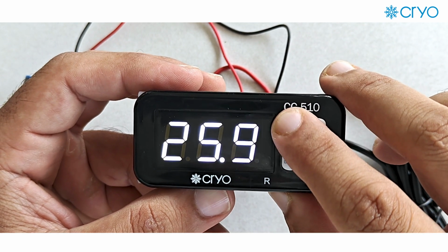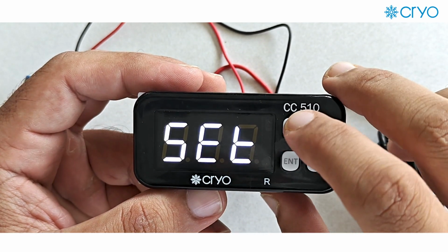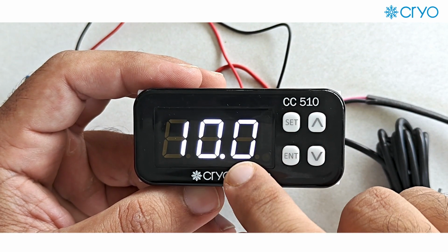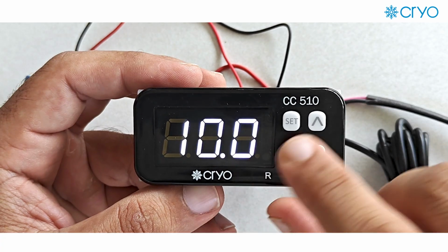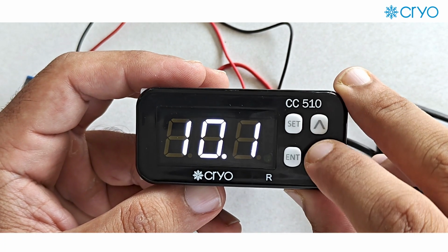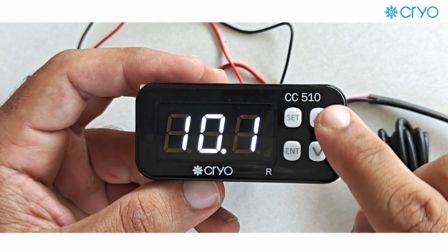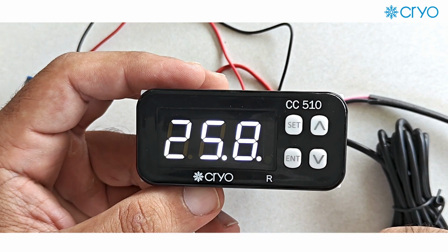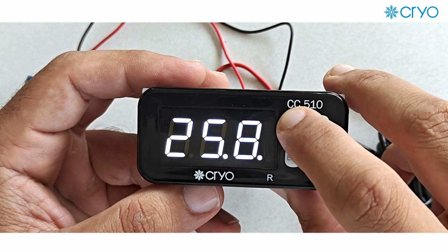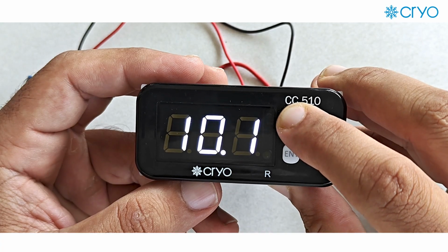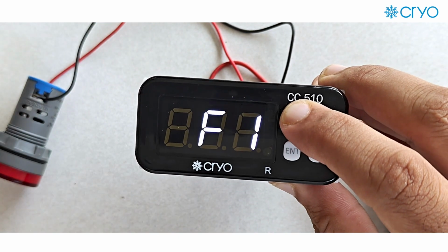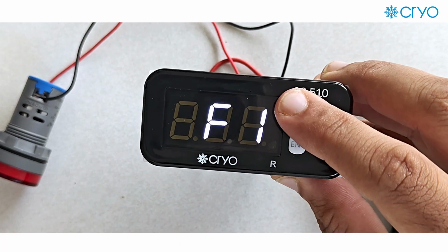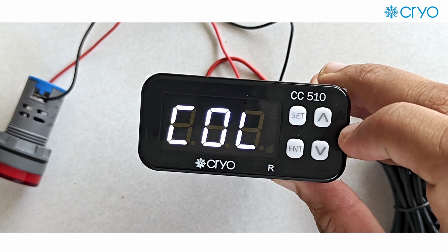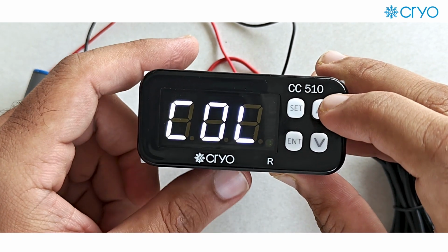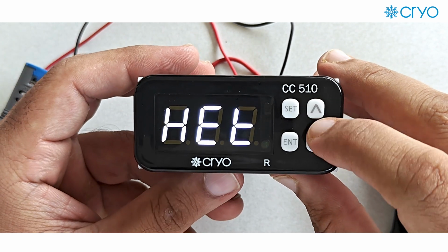Now if you press the set button once, it will show you the set value. Again set. So the current set value by default is 10 degrees Celsius. With the help of up and down key, you can change the temperature of your CC-510. Now to go into the programming settings, we'll press this set button continuously. On the display F1 will come. So F1 is our mode selection. So you can set the instrument in cool mode or in the heat mode.